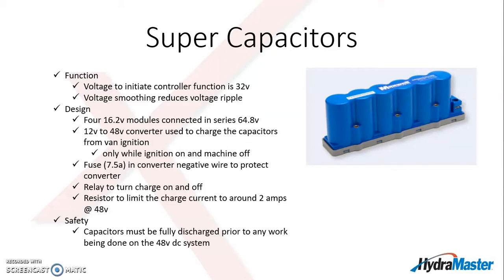Safety with capacitors. The capacitors need to be fully discharged prior to any work being done on them. There is some hazard of arcing, some shock hazard. Primarily, they say with capacitors, it's a burn hazard because they will discharge very rapidly. Much like a battery, if you short out a battery, positive to negative, you will get some arcing. You also get that with capacitors, but they're capable of very high current. So anytime any work is to be done on the capacitor pack, they really should be discharged completely. We'll go over that discharge procedure.